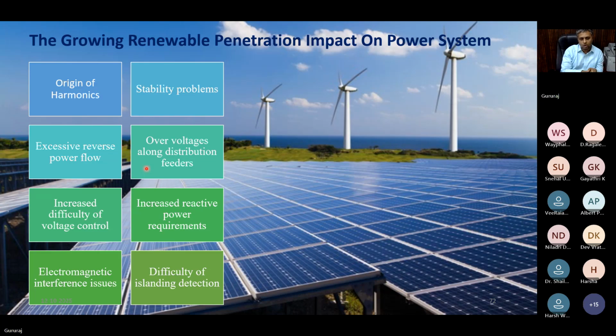So over voltage along distribution feeders, especially weak grids and rural feeders, is quite a challenging problem. There are also increased reactive power requirements as you bring more renewables into the system. Some reactive power requirement would be there anyway, even in the case of a wound-rotor induction machine with back-to-back converters, they may not meet the expectations - some reactive power consumption from the grid may be there all the time.